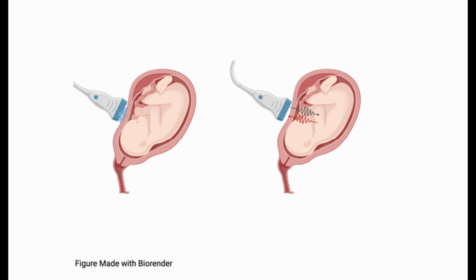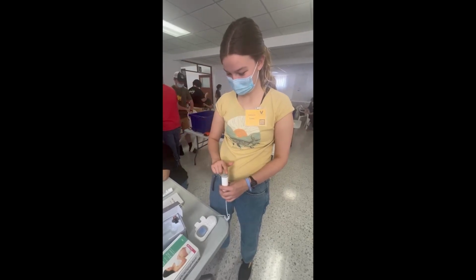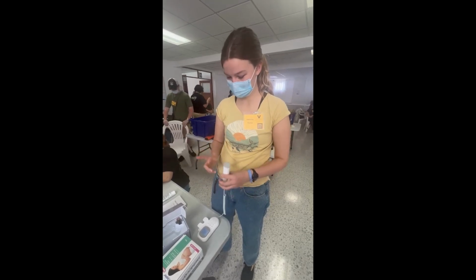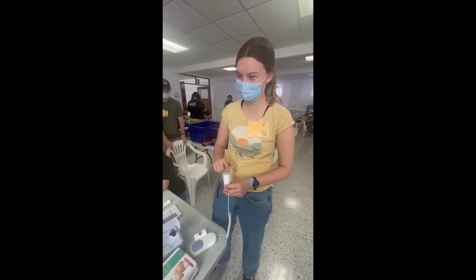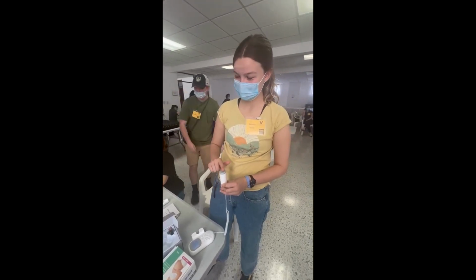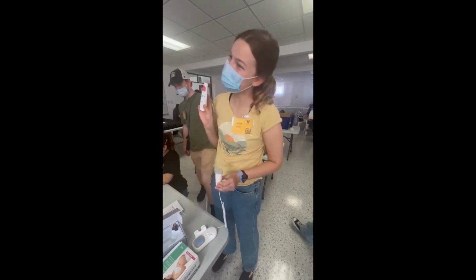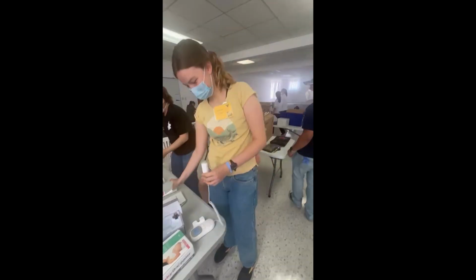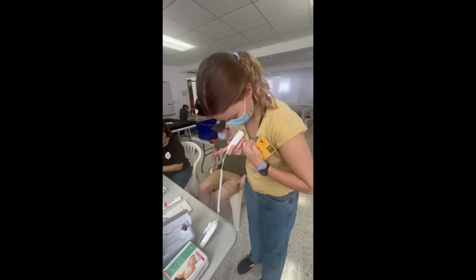This sound wave is emitted from the transducer and travels through the skin to the fetus. To make sure the sound wave can get to the skin, a gel is used to fill any minute air pockets between the ultrasound probe and the skin. The gel is important because it ensures the sound wave gets to and through the skin without significant reflection at the boundary between the probe and the skin.